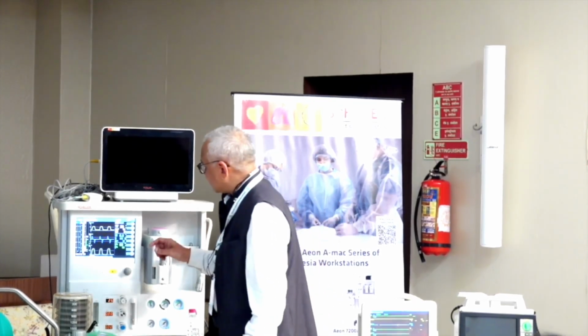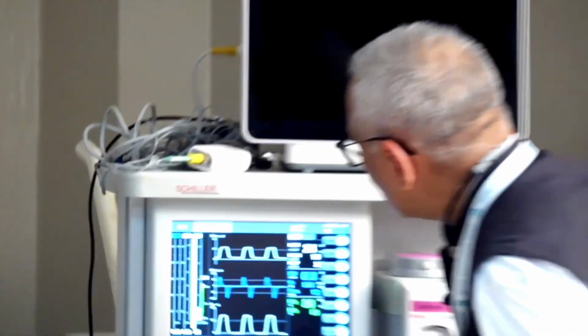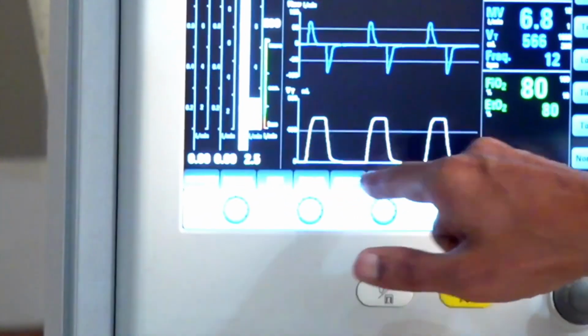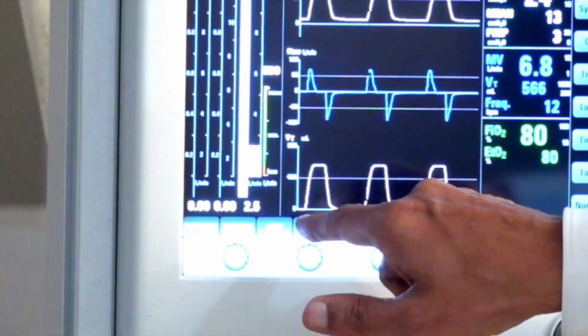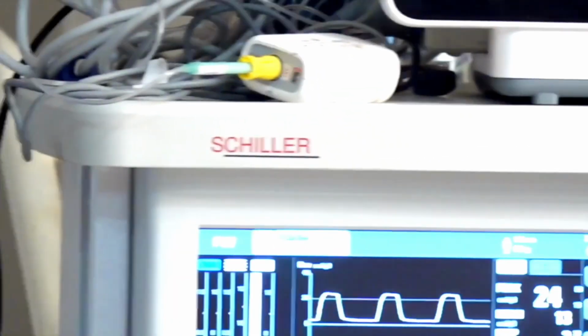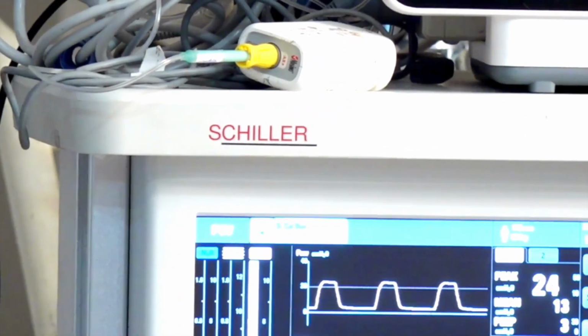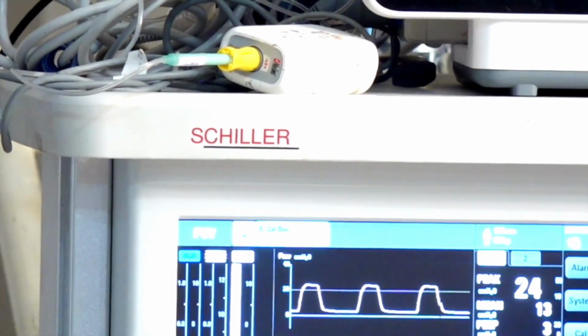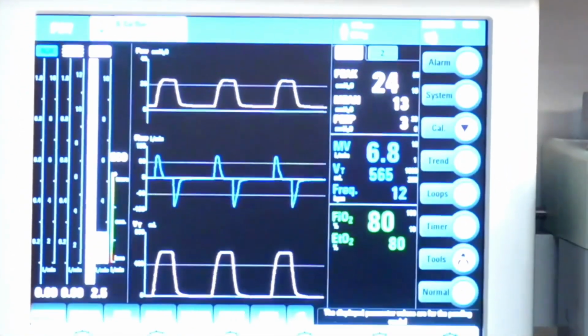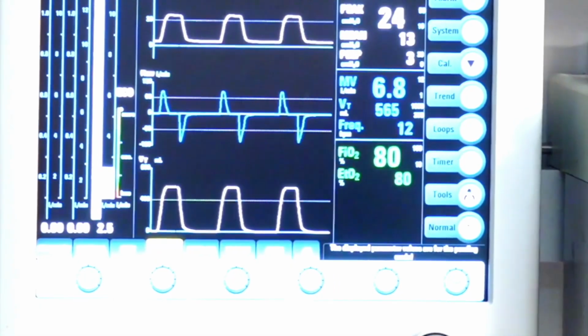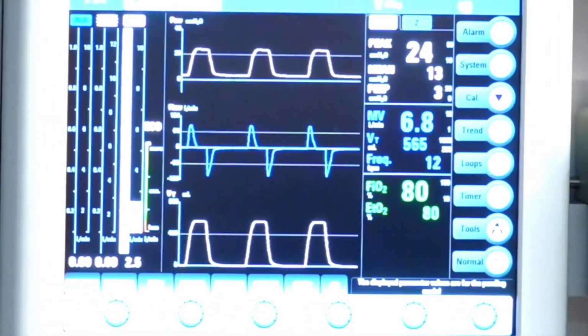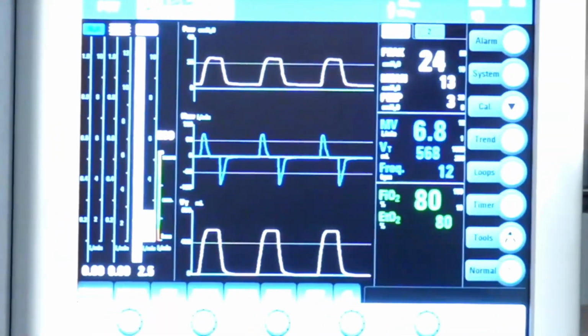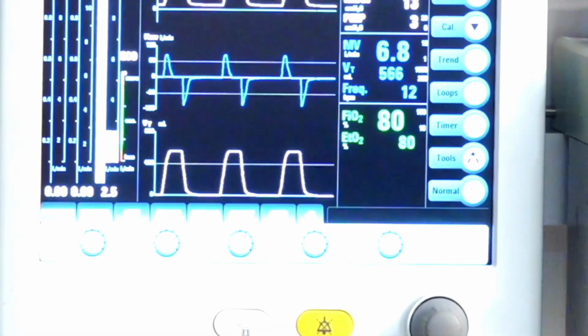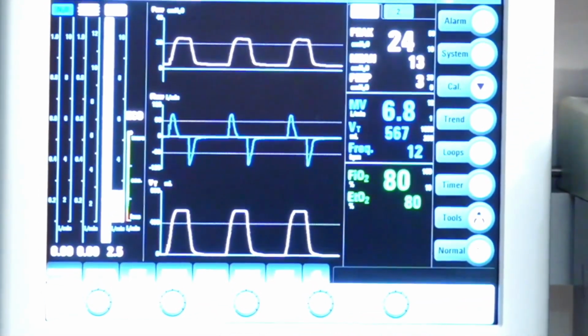So for that, now there is a newer mode which is called PCV VG. Okay. Now this is volume guaranteed mode. Some of the machines call it volume autoflow. Nothing, I'm just explaining. Volume autoflow. So we consider that it is a controlled ventilation with autoflow. They are basically pressure controlled type of mode with volume guaranteed within the specific range of airway pressures. So up to 35 it will try to give you your tidal volume.